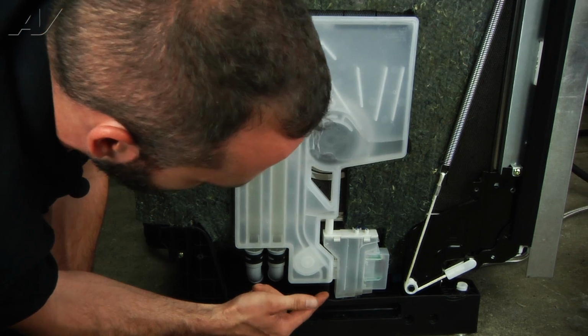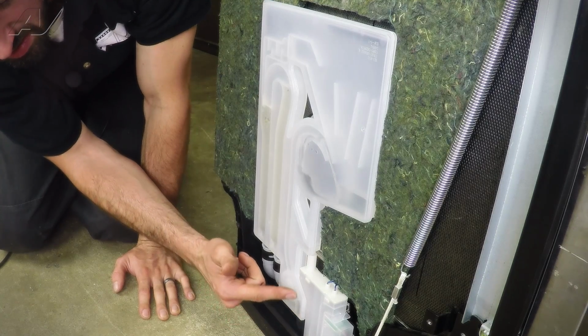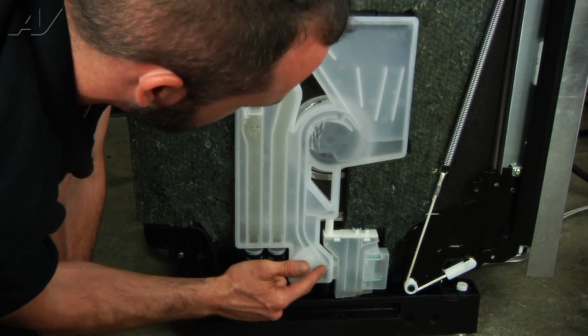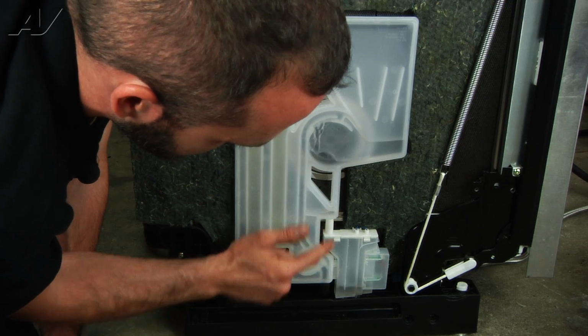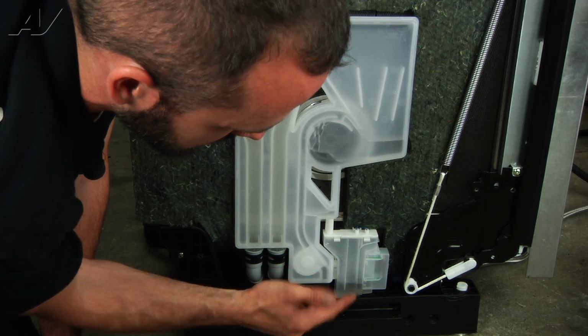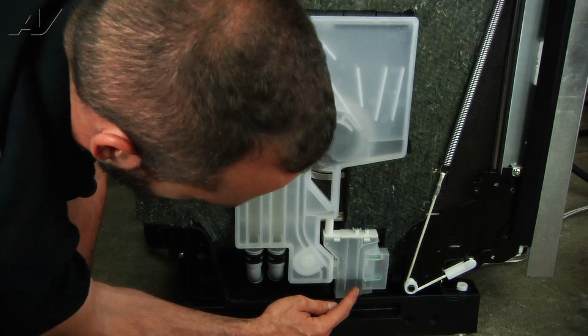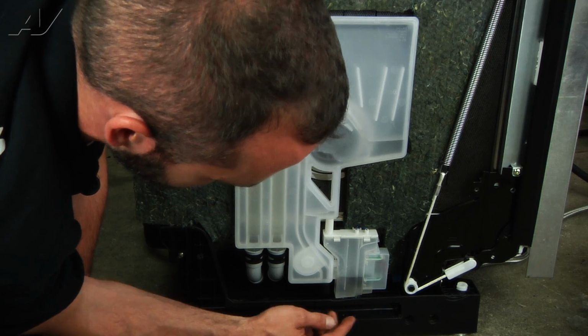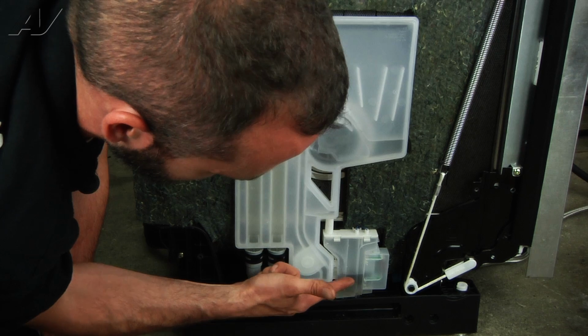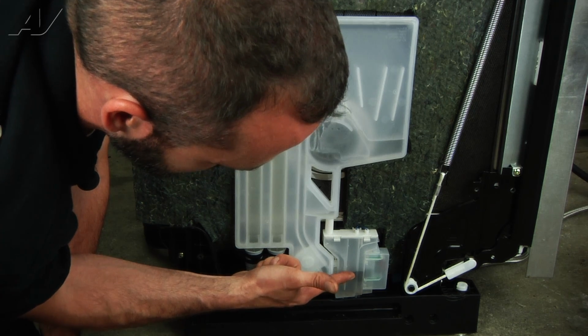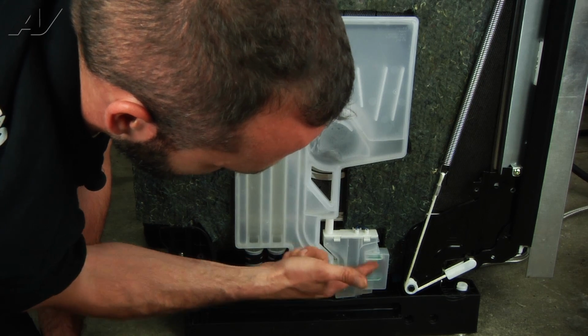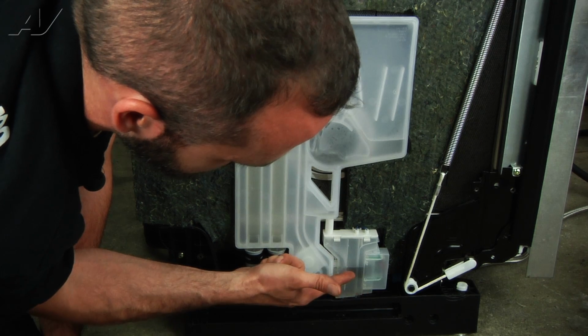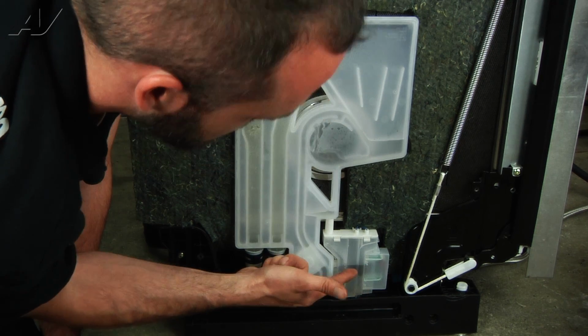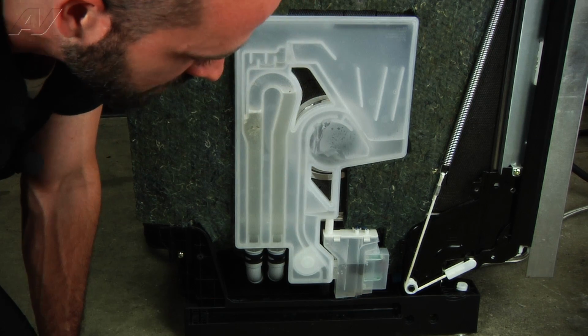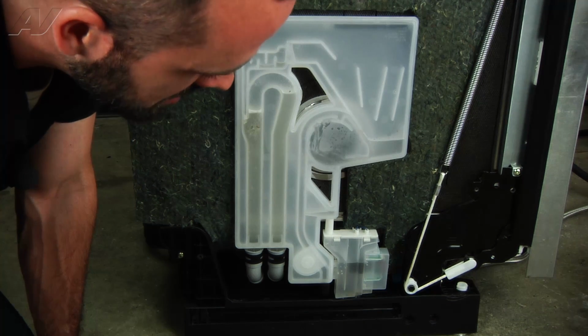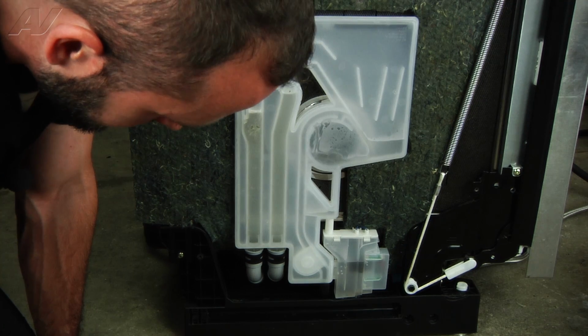And you're gonna see your water's coming in right here. And that's gonna be spinning this wheel and coming up through here, and it's filling this chamber here with water. And there's your float right there. As the chamber fills up, you'll see your float starting to come up. And that's basically gonna be in between these two boards here. That's gonna kind of let the unit know how much water is actually inside of the unit.